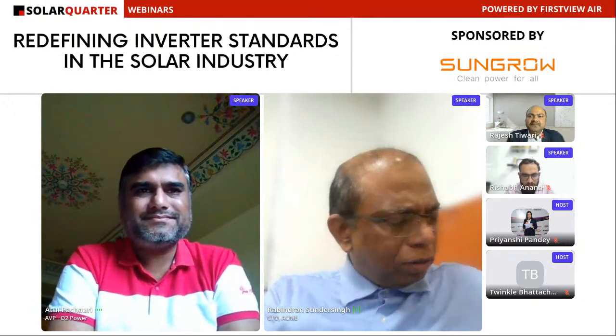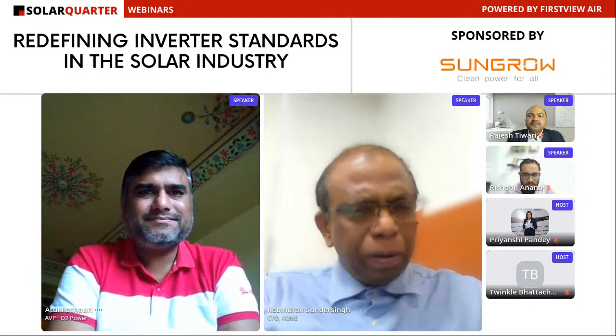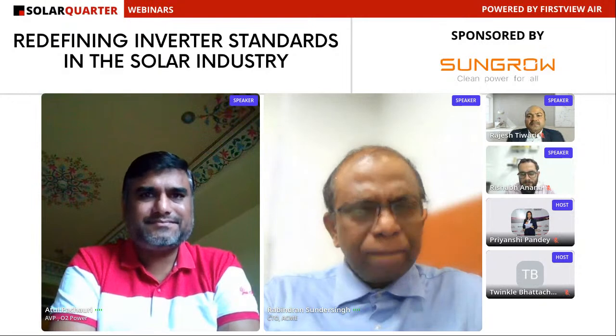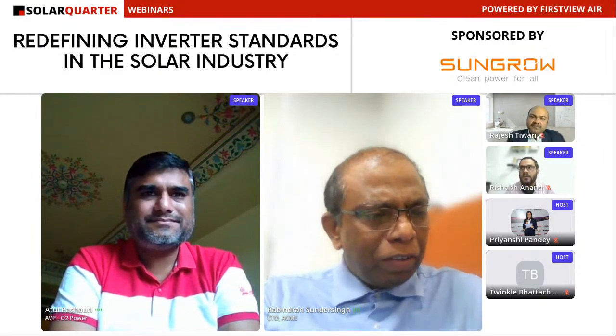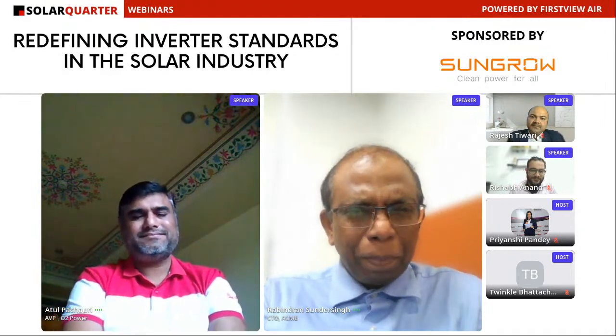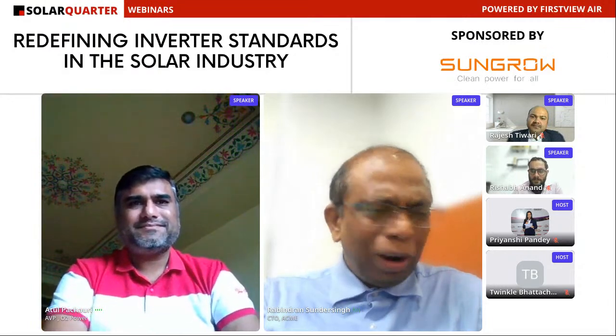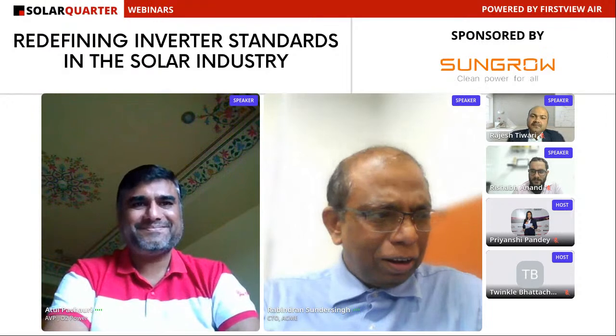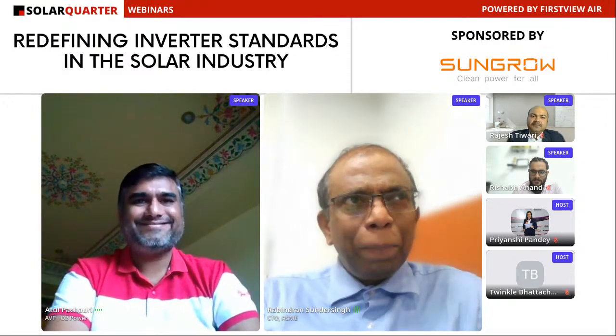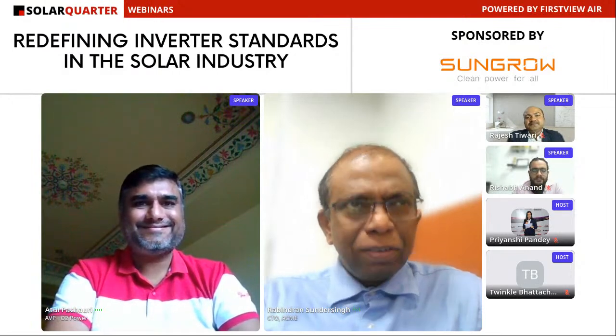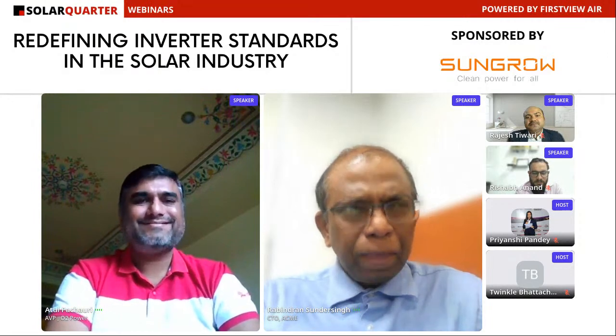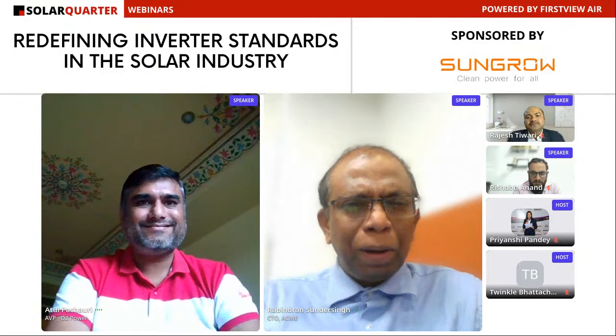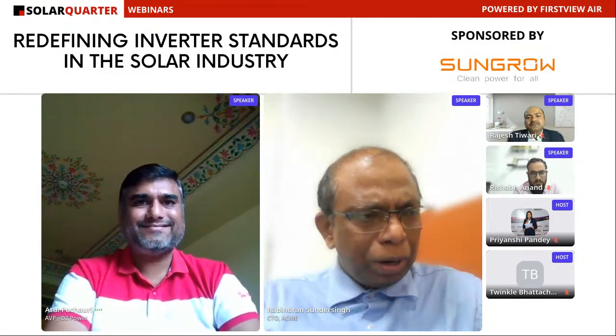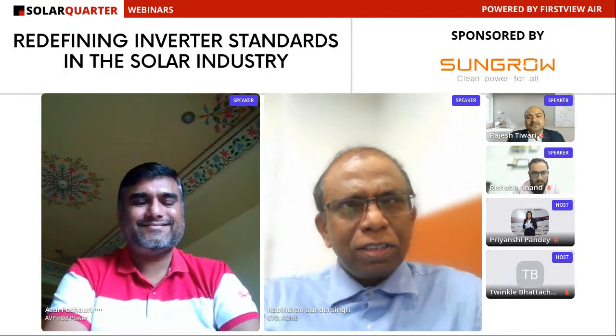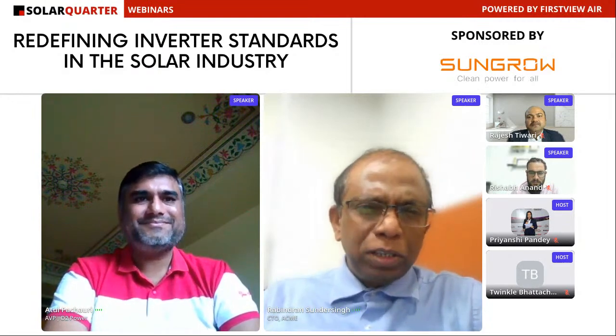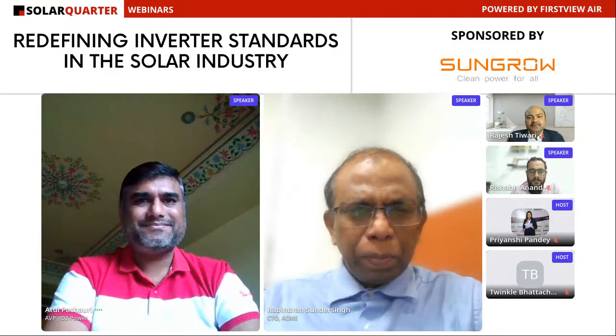So I do find that central inverters are better equipped to respond to grid situations. But on the flip side, with string inverters, I love that when I commission a plant for the first time, on day one, I know exactly out of my 1 lakh strings which ones are not working and which require what intervention. One of the biggest losses for IPPs is the first few weeks or months wasted in literally recommissioning the plant. I hate the concept that we commission something but it isn't really commissioned. In such cases, the string inverter really helps in visualizing totally where my generation loss, if any, is going.